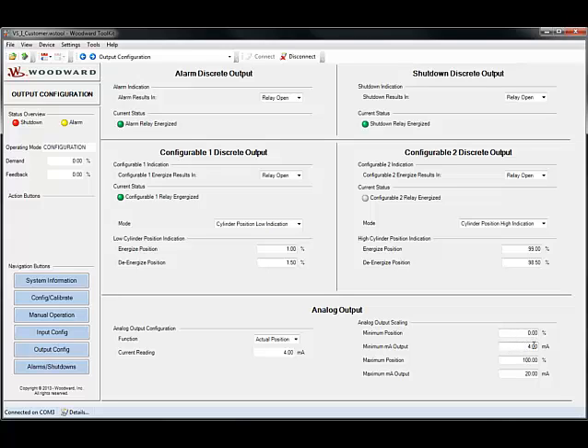This is saying that the analog output will now output 4 milliamps when the actuator position is at 0, and 20 milliamps when the actuator position is at 100.